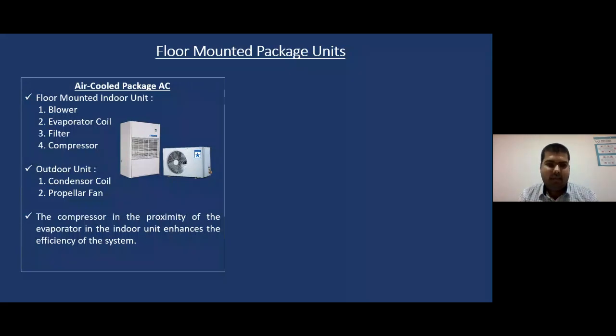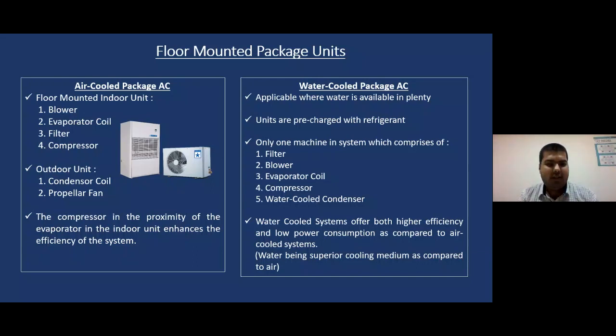Water-cooled package AC. Water-cooled package ACs can be used, for example, where water is plentiful. First of all, units are pre-charged with refrigerant, and it is basically a single standing machine which has all the components: filter, blower, evaporator coil, compressor, and water-cooled condenser. Only this machine would be directly connected to my cooling tower. Water being a superior cooling medium as compared to air, water-cooled machines obviously have higher efficiency, and they give lower power consumption. And they have a long life as compared to air-cooled machines.